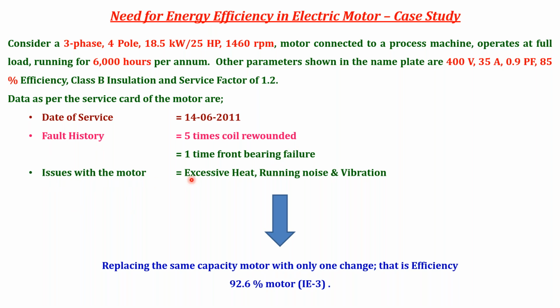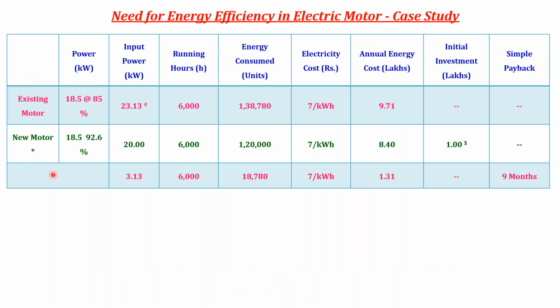Assuming that the motor has excess heat during running, and it generates noise and vibration. Now you want to replace the motor, or you are going to suggest replacing the motor with an IE3 motor having an efficiency of 92.6%. So you can put a simple table: what is the present nameplate power, and what is the power taken by the motor.